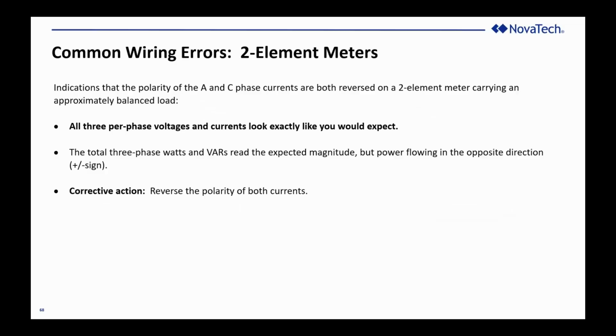Suppose the polarity of both the A phase and the C phase are reversed on a 2-element meter carrying an approximately balanced load. Well, this is much like you would expect. If you reverse the polarity of both elements, all you're doing is showing power moving in the opposite direction, the same as changing the polarity on all 3 phases of a 3-element meter. It may be the policy of your company that power into the bus plus power out of the bus must equal 0. So you have to consider that that might be the explanation.